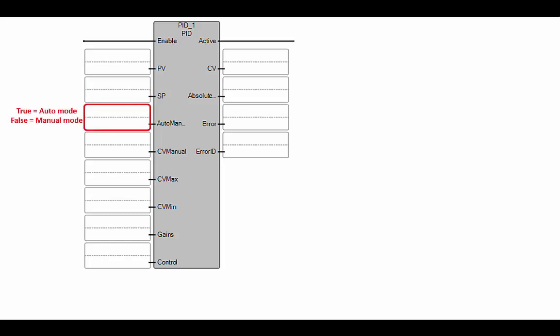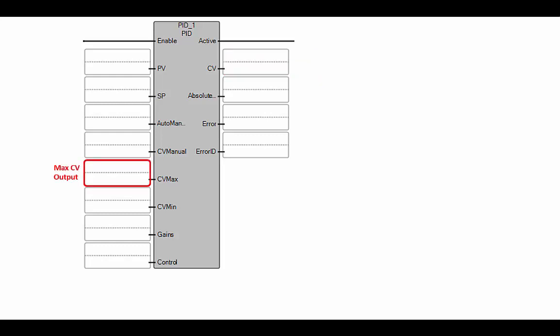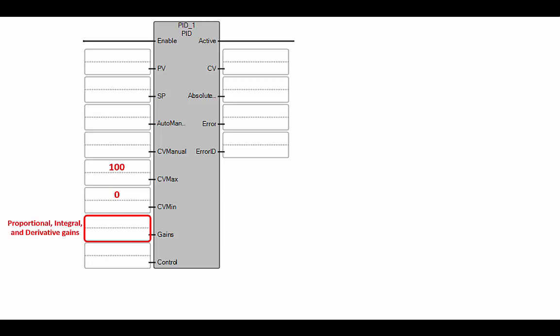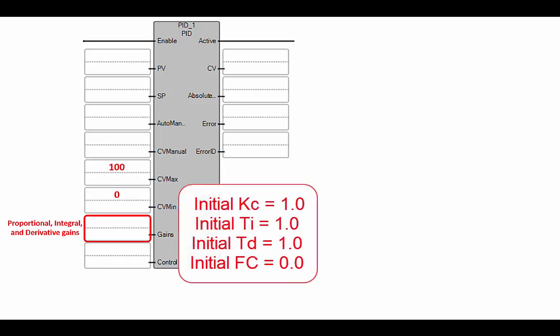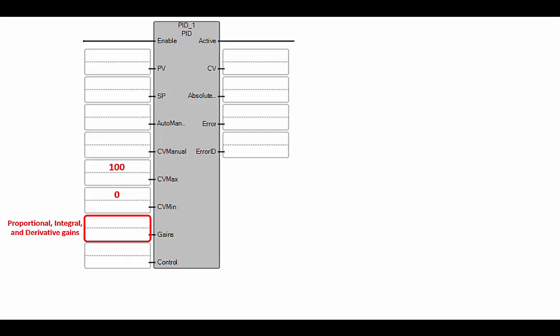The PID also has an input to specify whether it's in automatic or manual mode. In automatic mode, the control variable is calculated automatically based on the process variable, set point, and gains. The control variable needs a maximum and minimum bound set. Because we're using this PID with the auto-tuning instruction, we need the maximum CV output to be 100 — meaning 100% — and the minimum to be 0. The gains are the proportional, integral, and derivative gains, and we'll set initial values to 1 for proportional, 1 for integral, 1 for derivative, and 0 for the filter gain. These will then be updated based on the auto-tuning output.